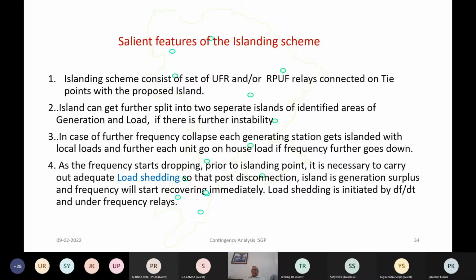And then, depending on the generation which is dedicated to this island and the load, you plan the balancing of the generation and load within the island. This island can then be further split into separate islands of identified areas of generation and load. If you are not able to manage the whole island, suppose Delhi as a whole, you island first by opening the tie lines, and there are a number of tie points with the grid to which Delhi is connected. You have to keep certain generating units and their respective corridors connected to this island, isolated, and dedicate those generators, and the load will have to be balanced.